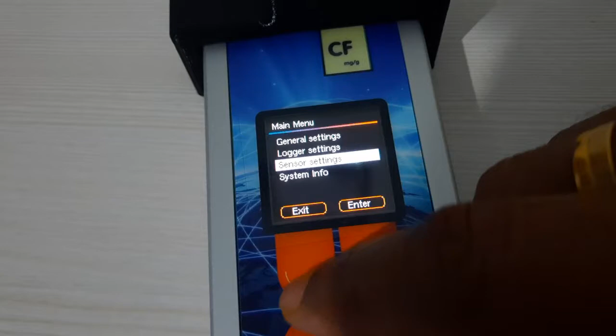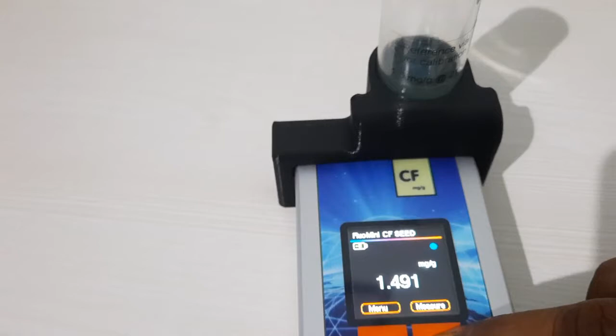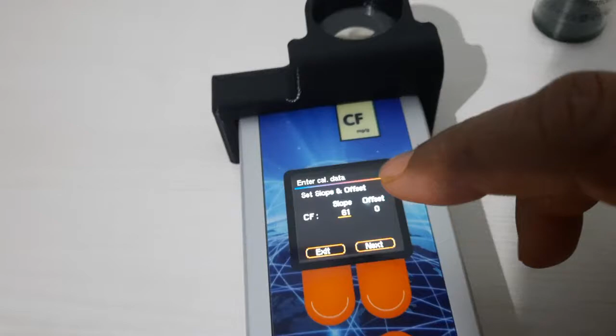So let me check it with the vial, measure. So it's 1.491 it is coming. So we have to increase the value a little bit. Just a moment. Menu, enter. Sensor settings, enter. Enter calibration data, enter. Slope, it was 61 is the base, so we have to increase a bit. So 63, 64 will do it, or we can keep it at 64.